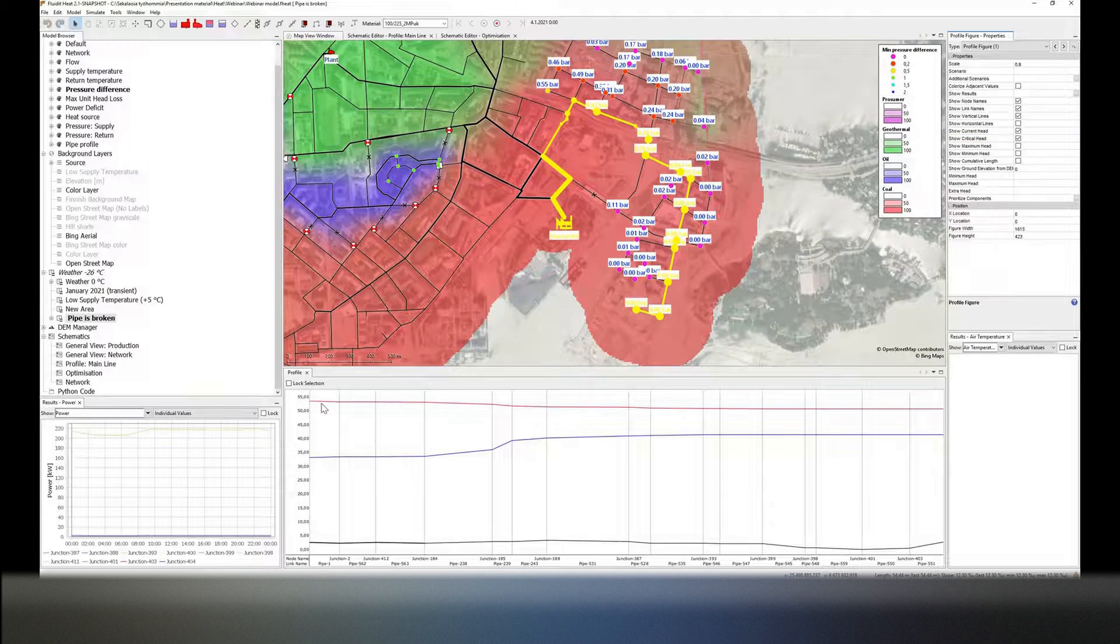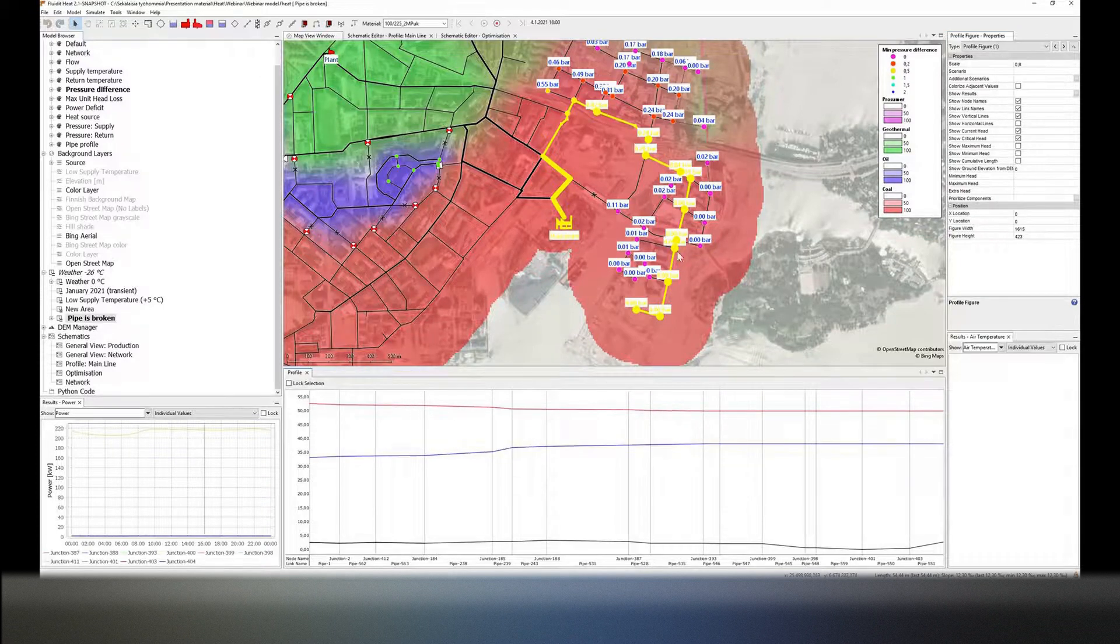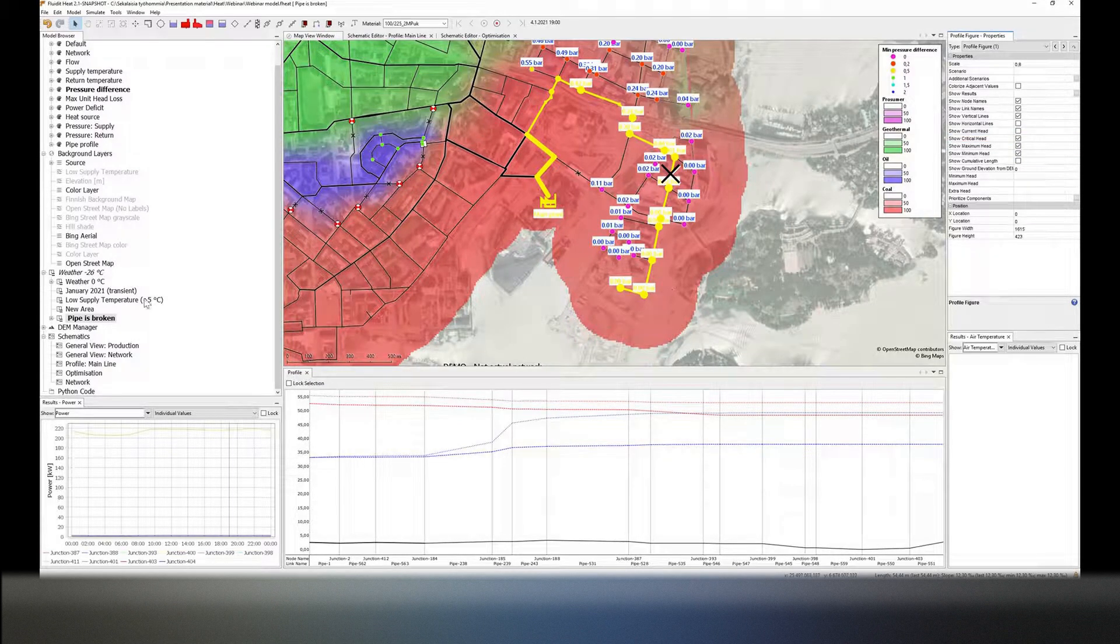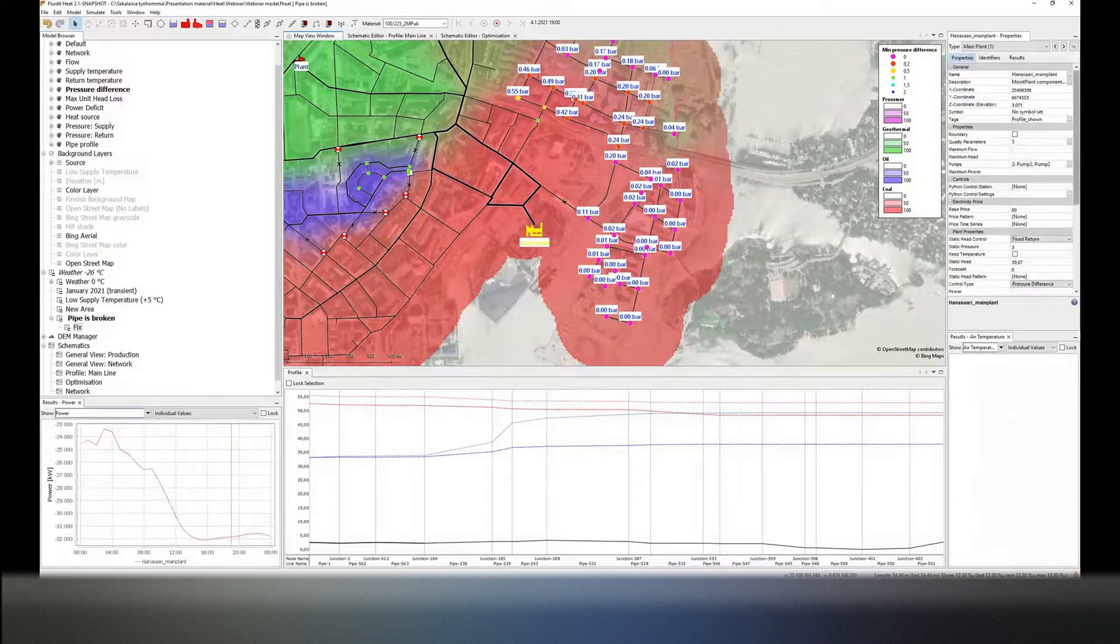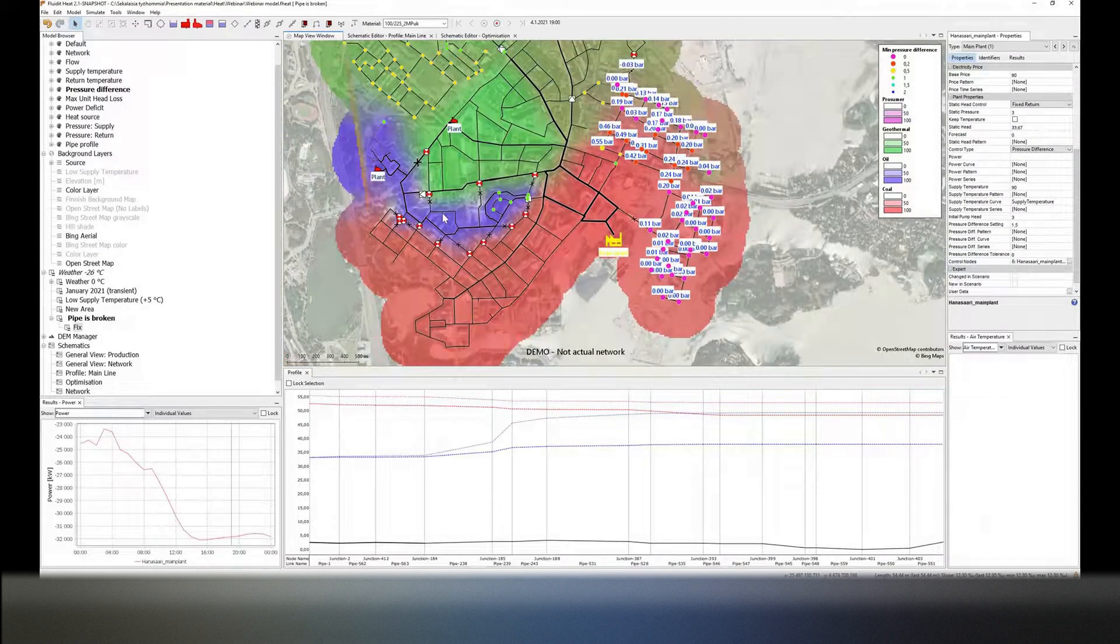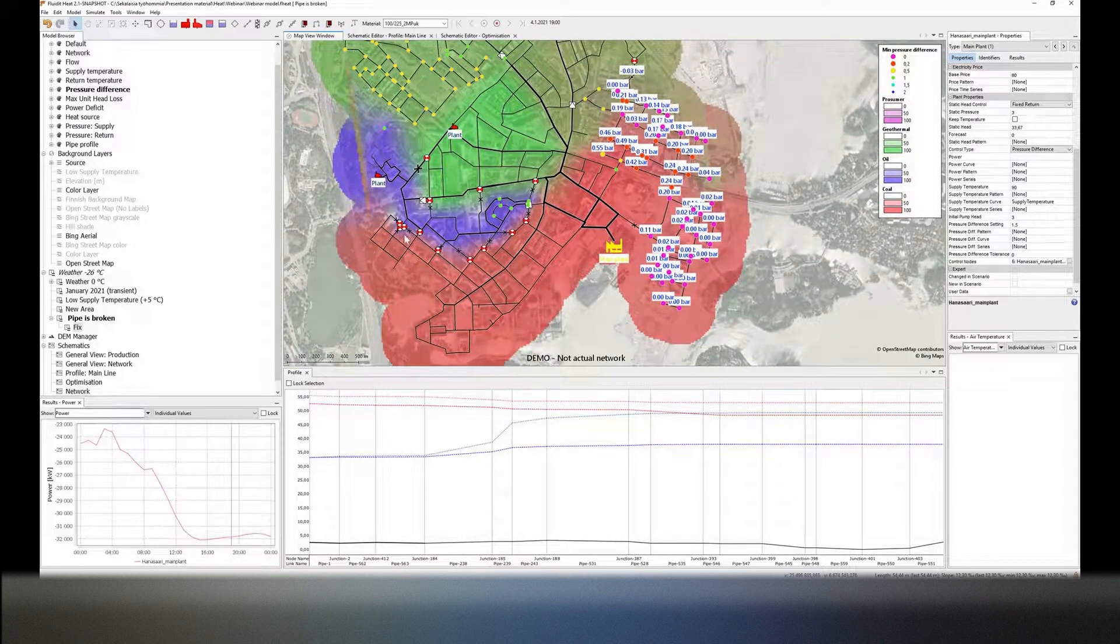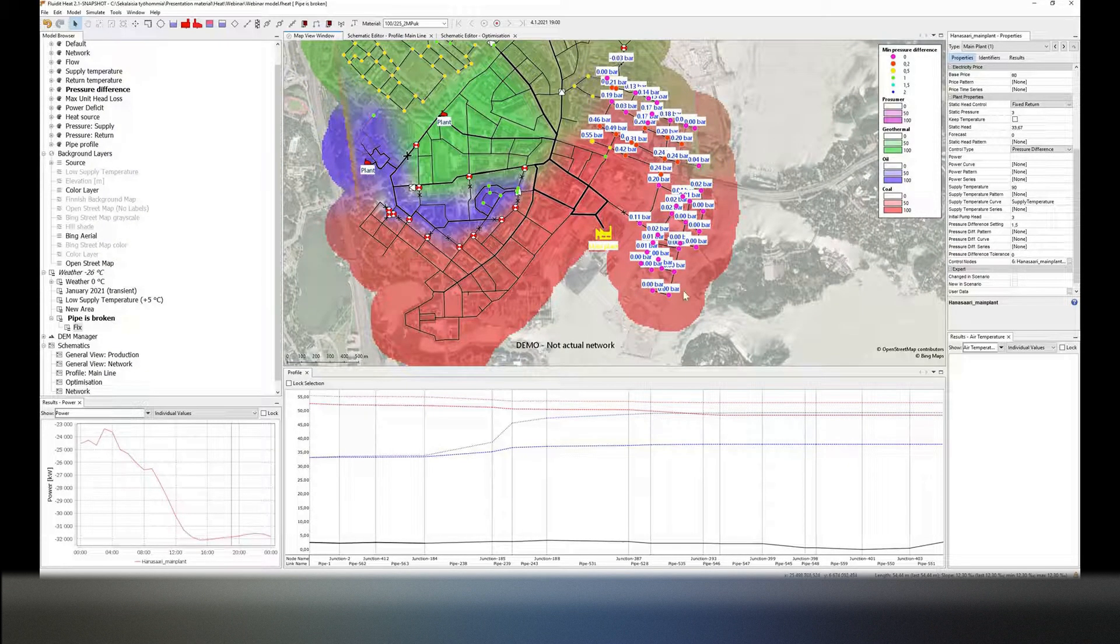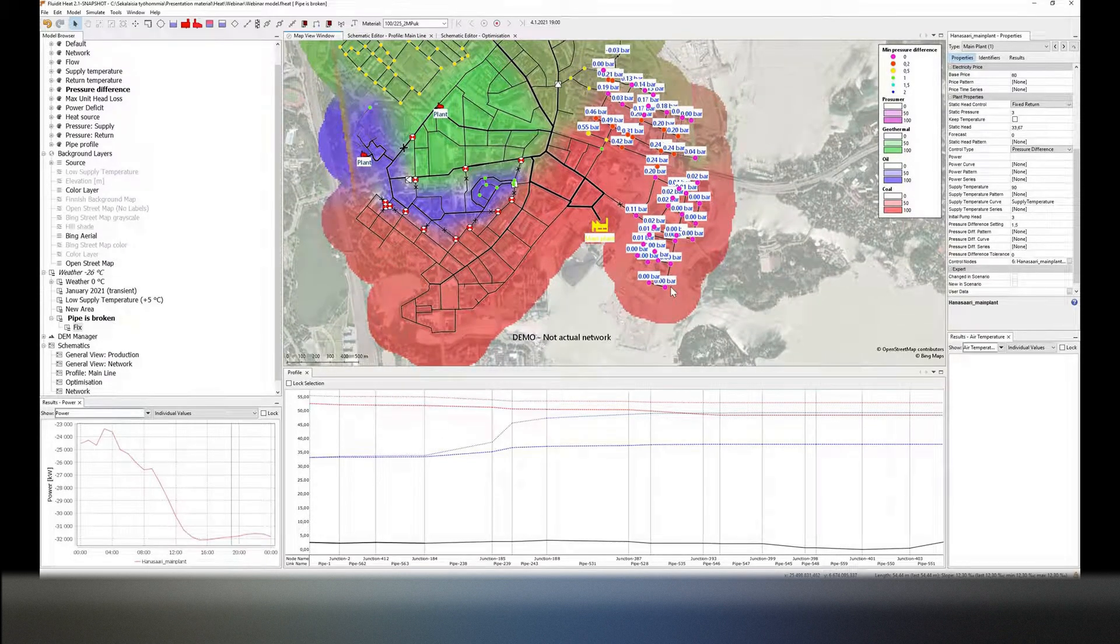The main plant supply is going and as it is taken forward in time, it is running into quite some troubles. But what is the fix then? Now the main plant, the way that it is functioning, is that we are looking at certain control nodes in our network, as most bigger networks are functioning. You are having control nodes and the plants are looking at those and keeping the pressure difference at the furthest point. But because our main plant isn't actually looking at any of these points in here, it doesn't care that these pressure differences are not met.